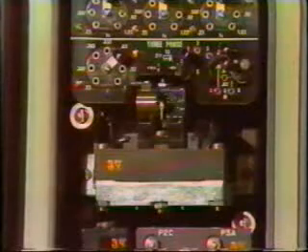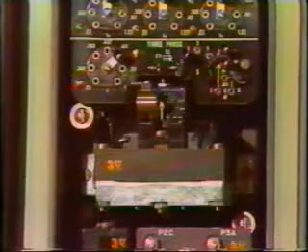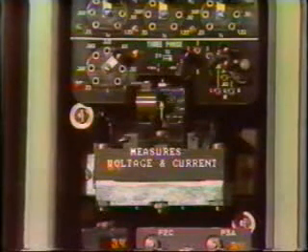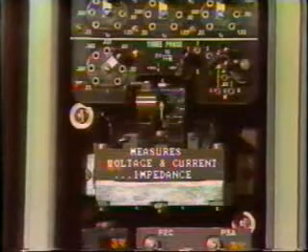On some large motor installations, an additional relay is installed to protect against locked rotor. This is the impedance relay. It is set up to measure voltage and current entering the motor, and so measure the impedance.